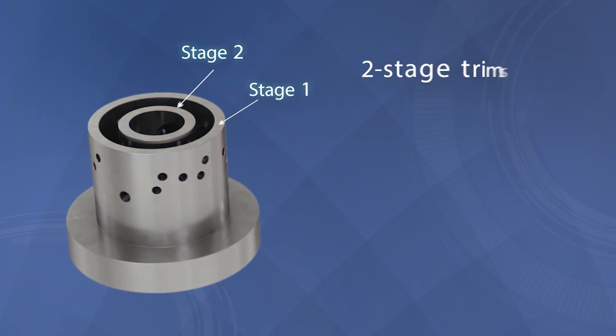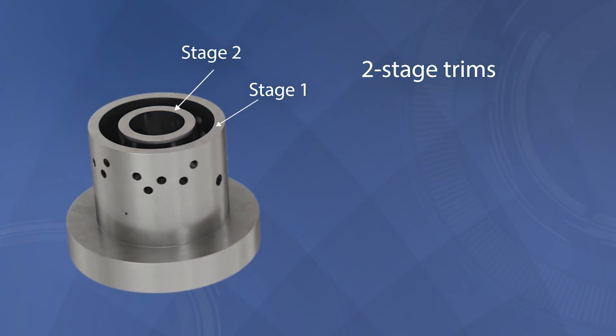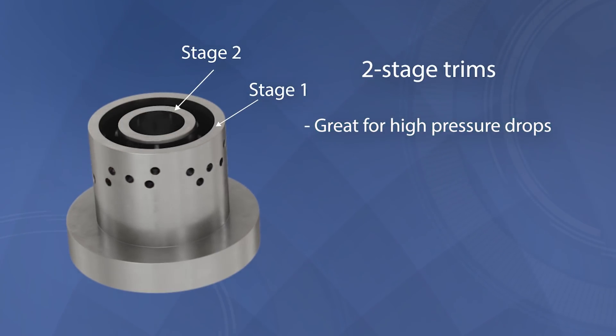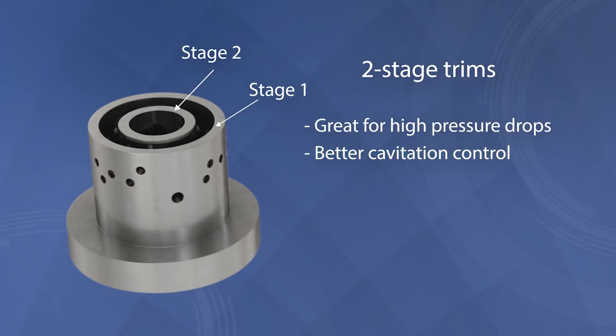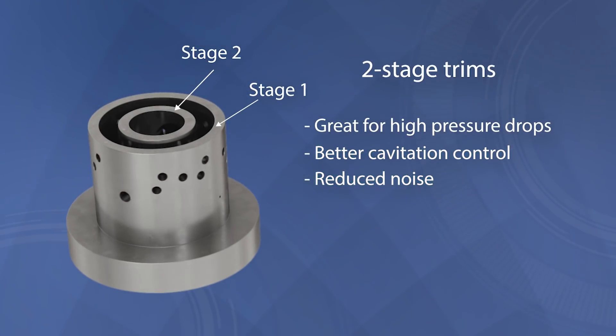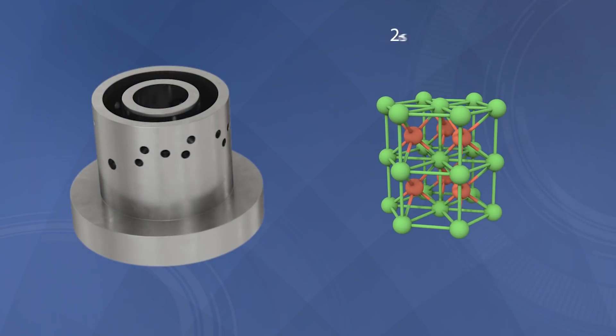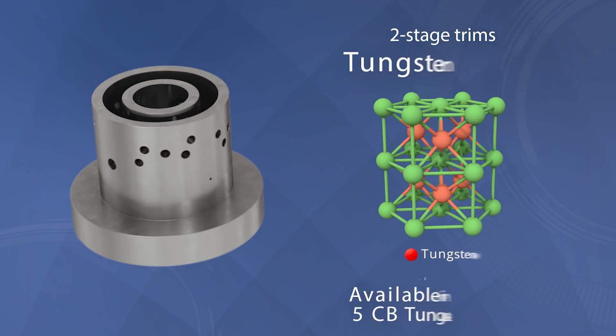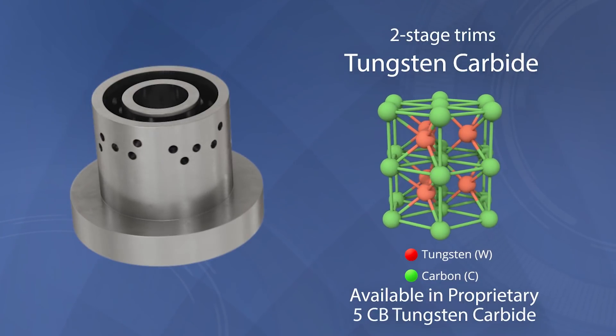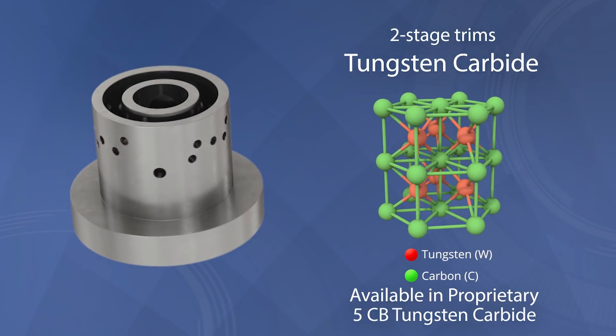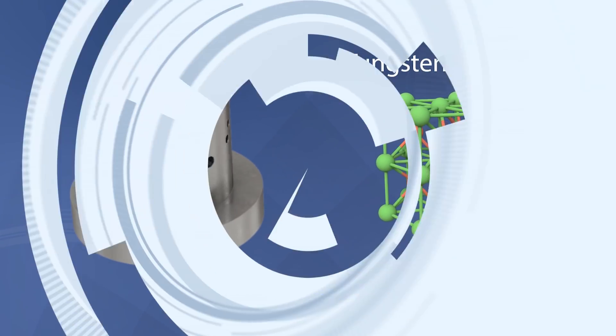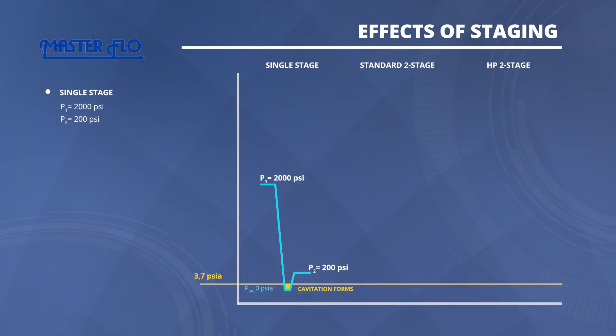For demanding applications with high pressure drops, two-stage trims can be used. They consist of concentric cages which handle pressure drops in stages, reducing the pressure dip at the Vena contracta. This results in better control over cavitation and noise. Master Flo's multi-stage trims are available in service-specific materials, including the proprietary 5CB tungsten carbide, for higher erosion and corrosion resistance. Multi-stage trims can also be engineered to provide custom flow curves, and the effects of staging can be seen on these graphs.